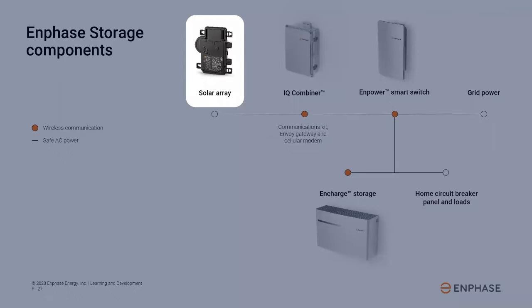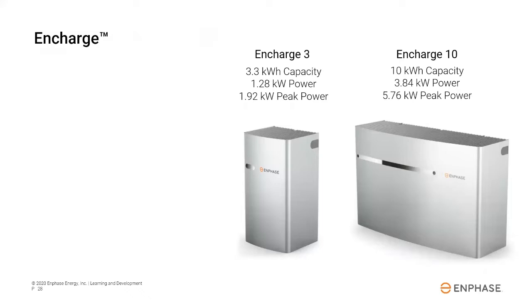And all Enphase storage systems will also have Enphase microinverters on the solar array. Our system is not currently compatible with other non-Enphase solar inverters. It all starts with the Encharge Energy Storage Systems with integrated IQ8 microinverters. There are two versions of the Encharge. The Encharge 3, which has a capacity of 3.3 kilowatt hours, and the Encharge 10 with 10 kilowatt hours of capacity.